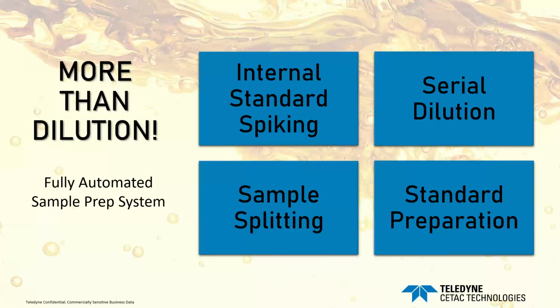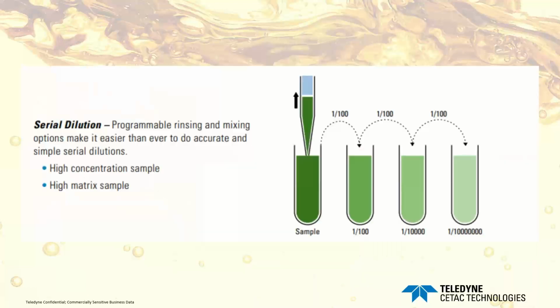But the SimPrep is not just a diluter. It can also spike, split, and serial dilute samples. It can even make your standards and calibration curves for you. So there's some real flexibility in the system as to what you can use it for. The serial dilution capability allows samples to be diluted to 1 to 10,000 and beyond. Such high dilutions may not be common in an in-service lab, but if the capability is ever needed, it is there.